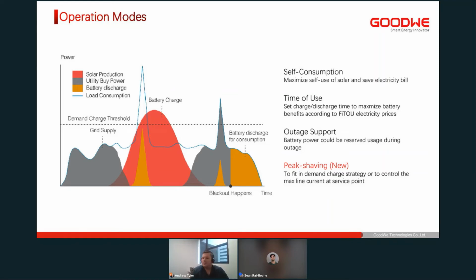We also have time of use, which is quite beneficial for those markets that have time of use tariffs, where you would have power that's more expensive during peak hours per kilowatt hour, and then you've got periods where the power is cheaper. So you would typically set your batteries to charge during cheaper electricity cost time, and do the exact opposite during more expensive times, which would be to discharge your batteries to the load. And then outage support. This is really a backup mode, which is more commonly used for my markets in Africa.